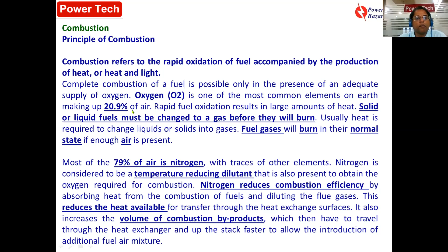That means if oxygen helps in combustion, nitrogen reduces the combustion efficiency. It reduces the heat available, and it also increases the volume of combustion byproduct. That means in the dry flue gas you will have CO2 as well as nitrogen. Because of nitrogen, you have higher ID fan loading, higher dust handling, higher gas handling equipment. So nitrogen is basically a temperature reducing dilutant, and it reduces combustion efficiency, whereas oxygen is required for complete combustion.